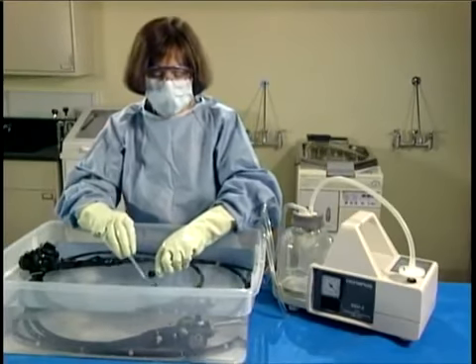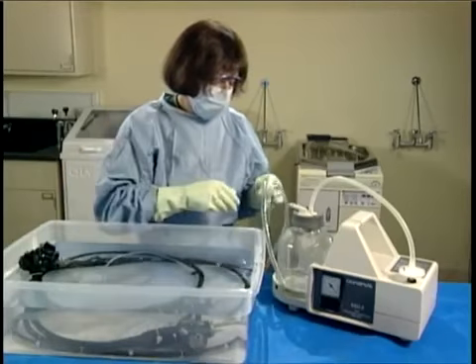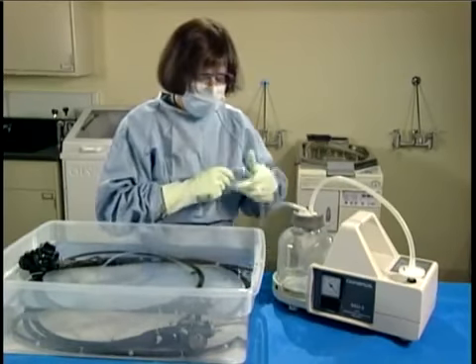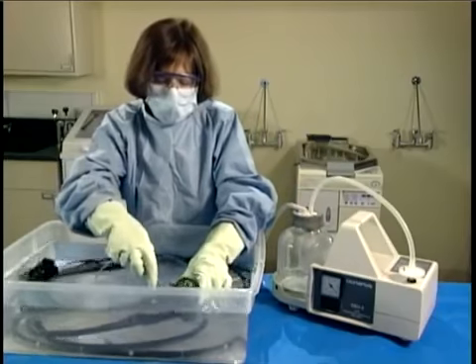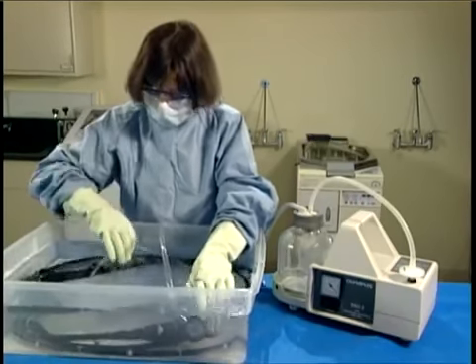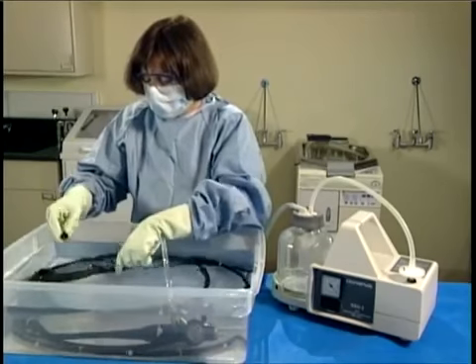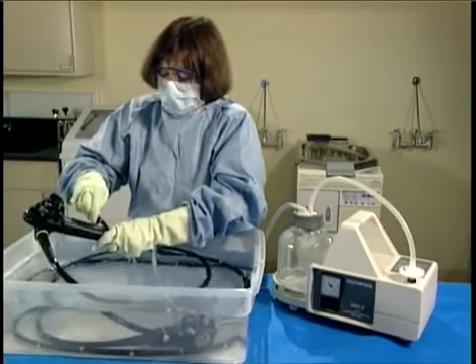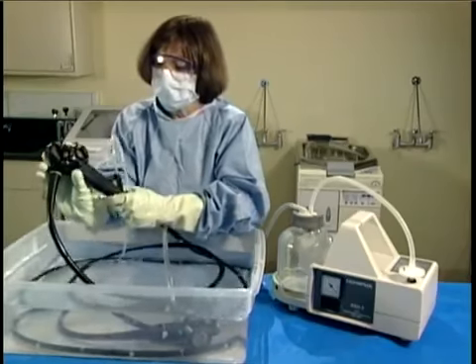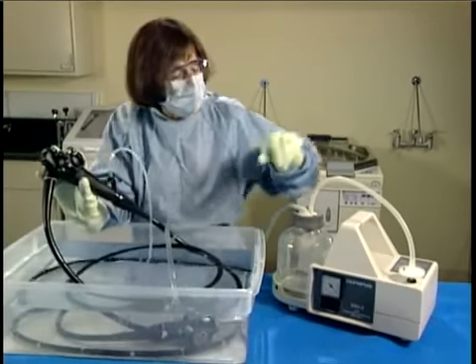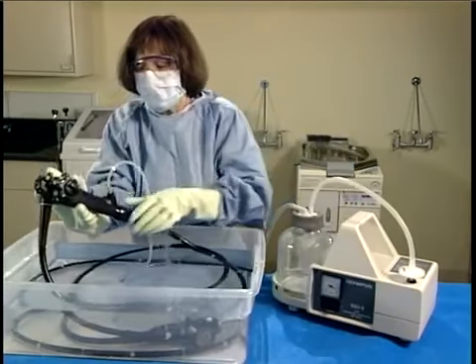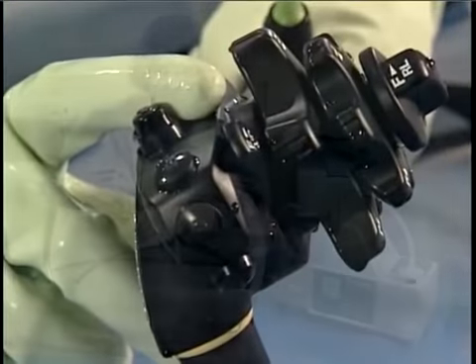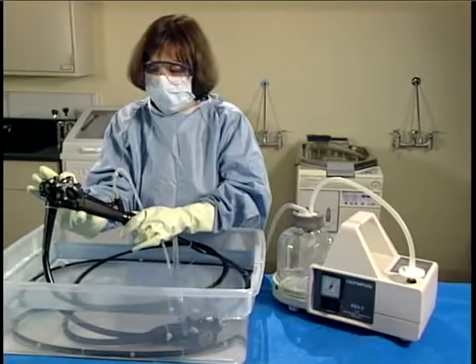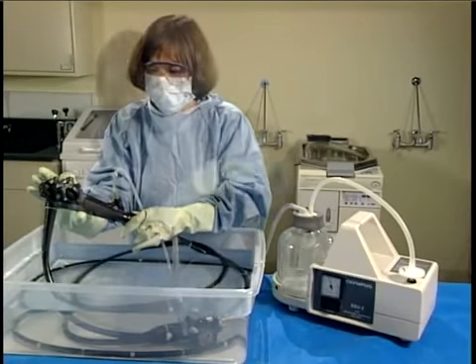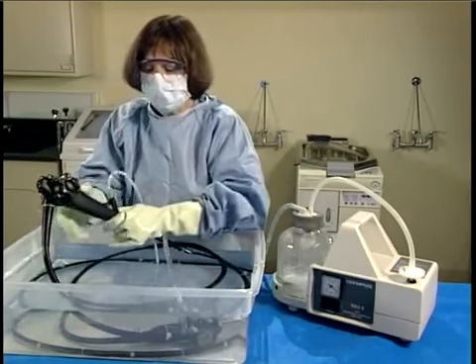Now that the channels have been brushed, the next step is to flush the channels with detergent solution to remove any remaining debris. Connect the endoscope to a source of suction. Attach the suction cleaning adapter to the instrument port. Immerse the distal tip of the endoscope and the weighted end of the suction cleaning adapter in detergent solution. Turn on the suction pump. Cover the suction valve housing with your finger and aspirate detergent solution for 30 seconds. Turn the suction pump off and disconnect the tubes.